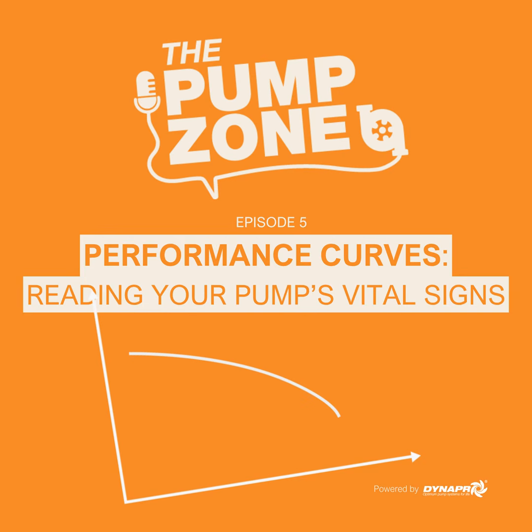Okay, so we've matched our physical incline, but moving all that fluid requires power, and that brings us to the physical limits of the machine. The sources talk about efficiency, power, and NPSHr curves. So the efficiency curve shows how well the pump turns electrical power into hydraulic work. It peaks at the best efficiency point, or BEP, which minimizes vibrations. And then the power curve is just used to size your motors, right? Exactly. And finally, you have NPSHr, which stands for net positive suction head required. That is the minimum input pressure you need at the suction side just to keep the pump fed and prevent cavitation.